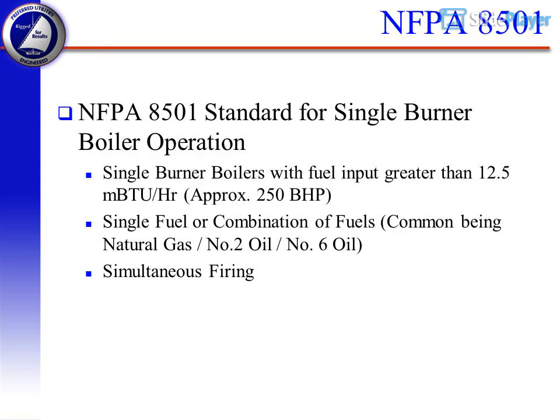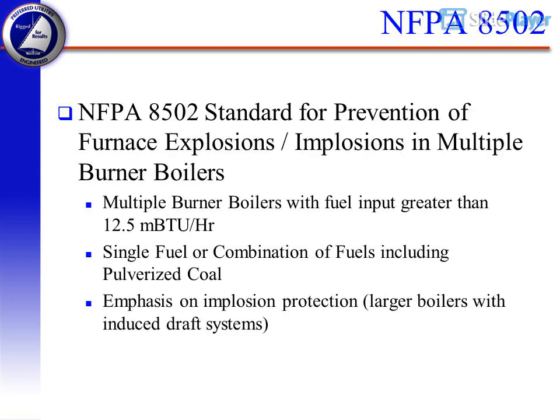NFPA 8501 Standard for Single Burner Boiler Operation. Single burner boilers with fuel input greater than 12.5 mBTU/Hr, approximately 250 bhp. Single fuel or combination of fuels, common being natural gas, number 2 oil, number 6 oil. Simultaneous firing.